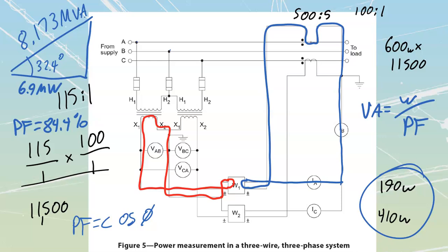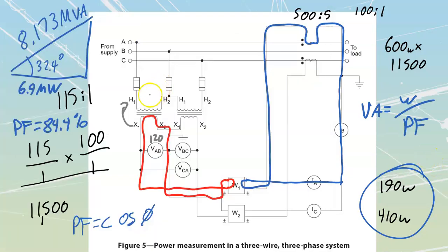It says that our secondary voltmeters all read 120. So we've got 120 that we are reading over here, and that they have a rating of 115 to 1. In other words, the high side is going to be 115 times that. So the 120, that's what I'm reading off of my PTs, times 115, which tells me that my high side over here is going to be a value of 13.8 kV. Beautiful. If I take a look at it, I see that I'm going across from A to B, so therefore 13.8 must be my E line.